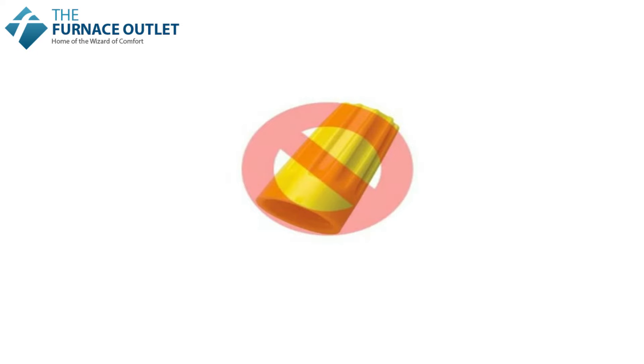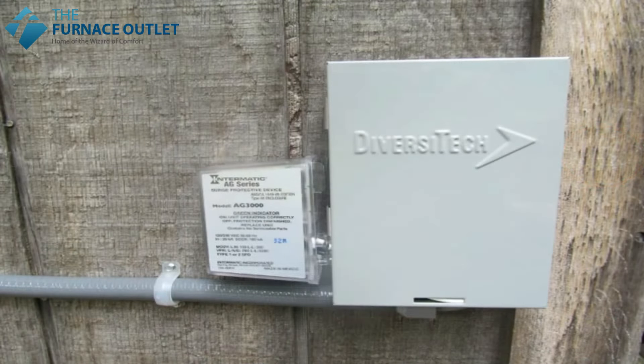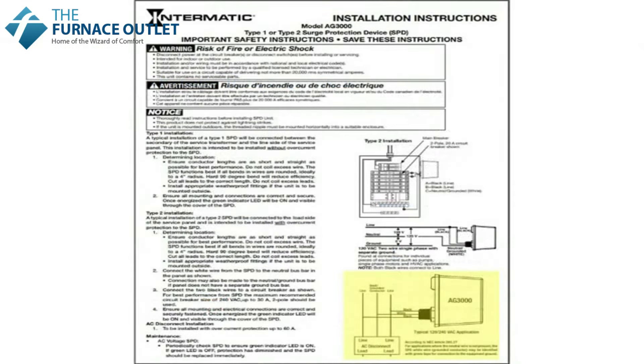Now replace the service panel on the right-hand side of the outdoor unit. Lastly, we need to connect the main power wires and conduit to a disconnect box — we're going to use one made by DiversiTech. I strongly recommend the use of a surge protection device, something like the Intermatic AG3000. It is a very inexpensive item that can save you thousands of dollars in lost equipment if the system were to experience a power surge.